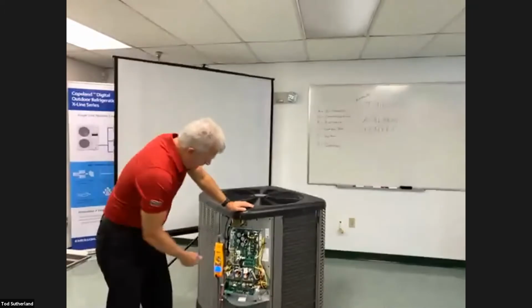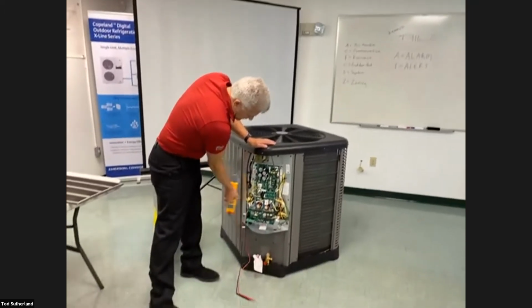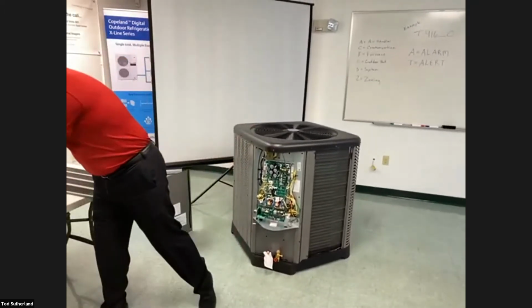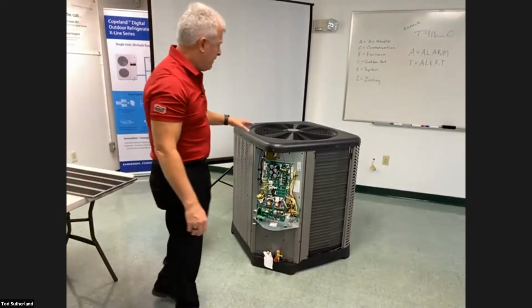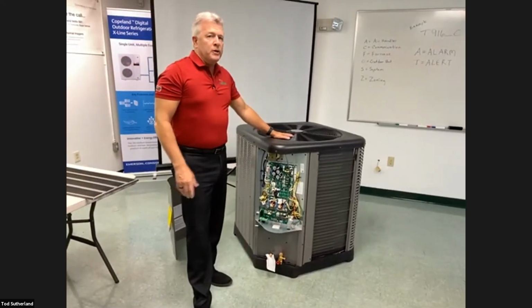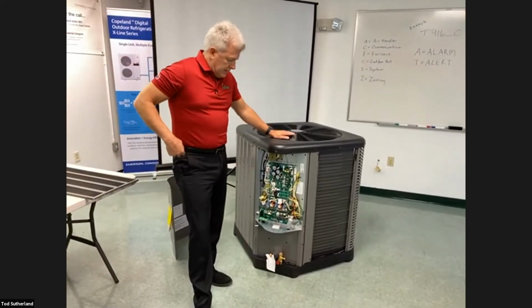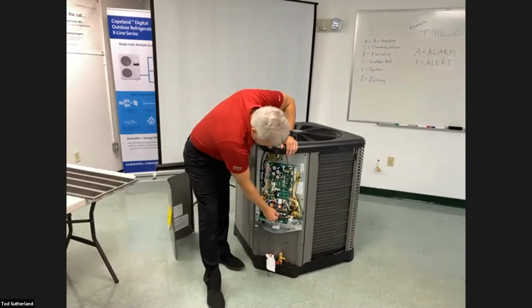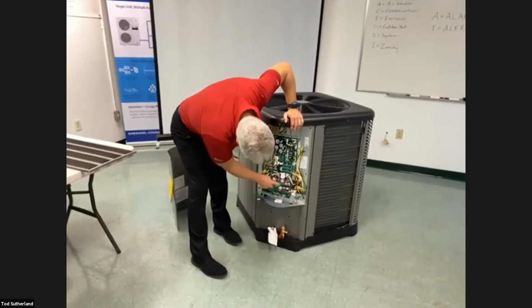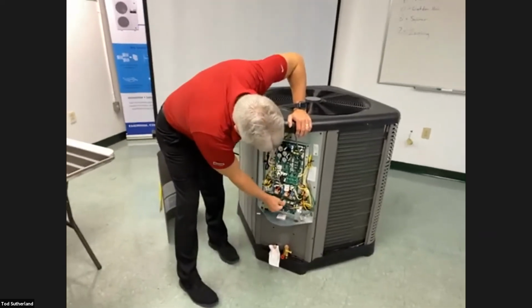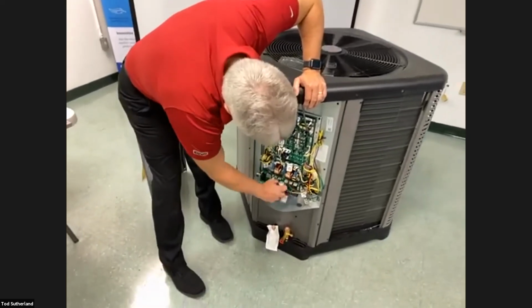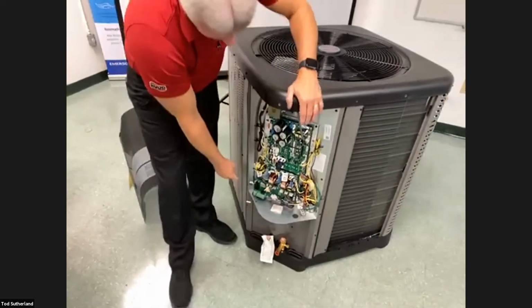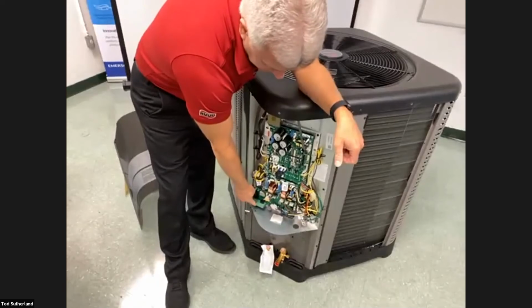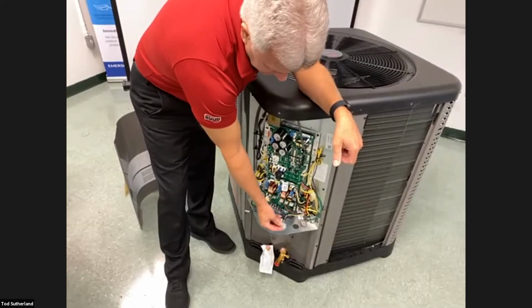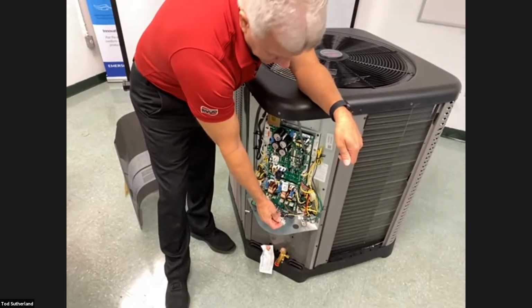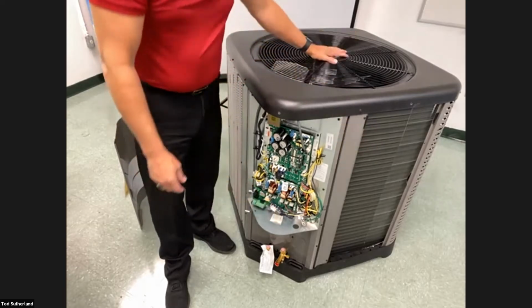One of the next features we'll go over on this is testing the blower motor. Testing the blower motor is really, really simple on these. You've got this blue and yellow wire right here. It goes to a tab that says fan, so you know that that's the fan motor. You'll simply unplug this and make a jumper between R and common, and jumper R and common to your blue and yellow wires here. Once you do that, the fan should run.